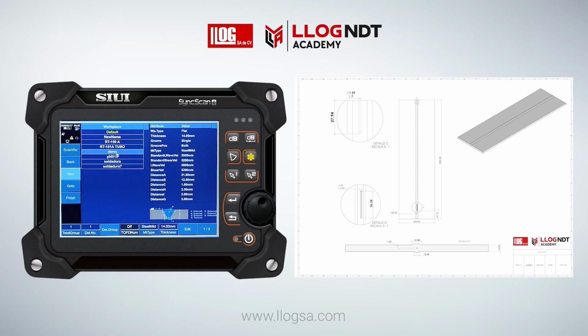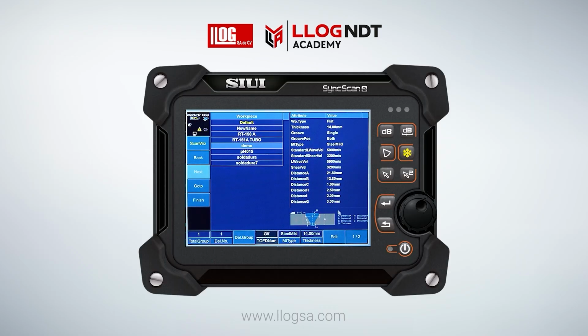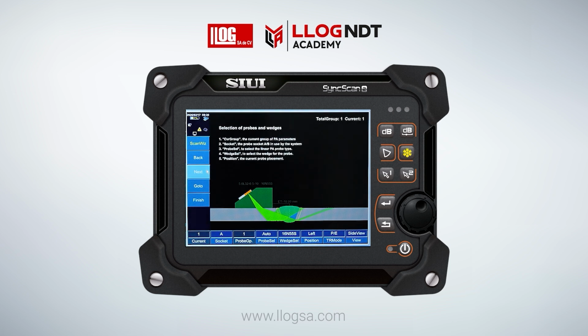Here we can see important information about the steel plate to be inspected, such as the thickness, which in this case is 14 millimeters. Next, we verify and complete the weld parameters, such as bevel angle, root opening, and cap height, among other parameters required for proper configuration. Once the weld dimensions have been configured, press the Next key. In the next window, we can see that the instrument has automatically loaded the transducer and wedge parameters. This is because distance, delay, and sensitivity calibration were previously performed.